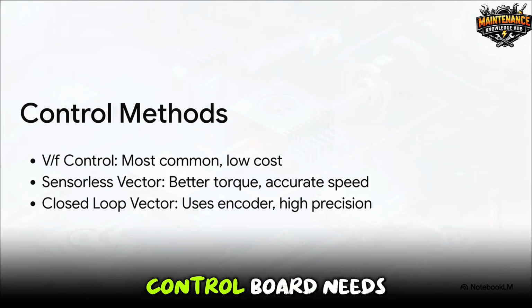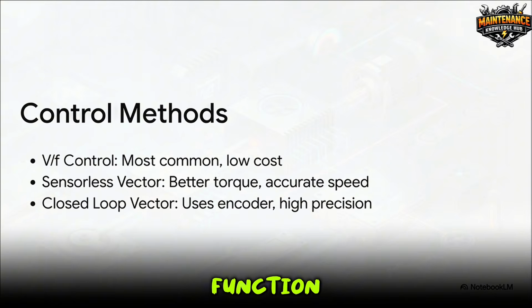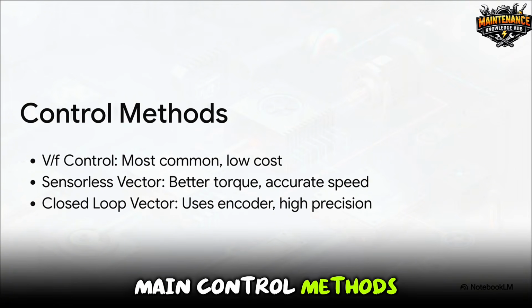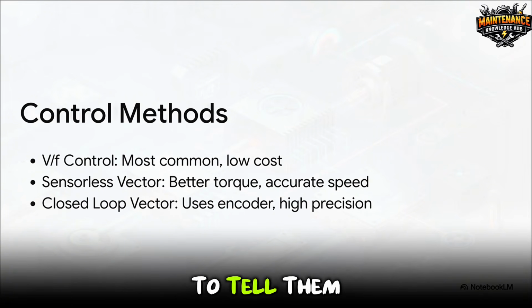But that control board needs software instructions to function. There are 3 main control methods programmed into VFDs to tell them how precisely to command the motor. First is V/F control, or volts per hertz. It's the most common, lowest cost, and it's perfect for standard centrifugal pumps and fans.